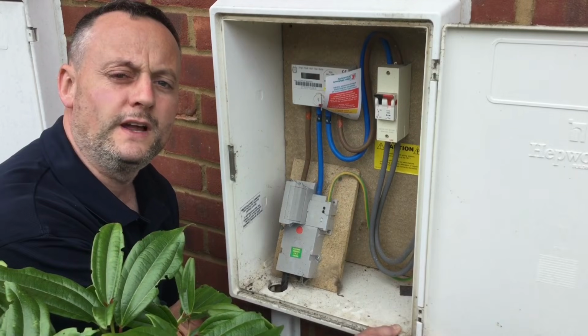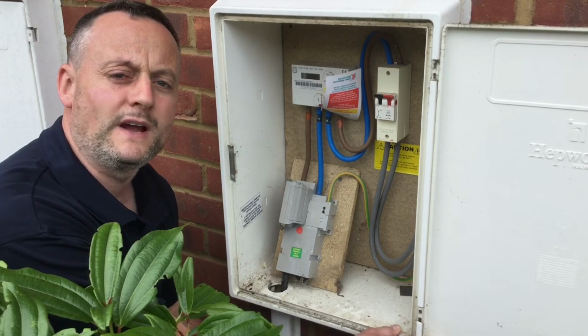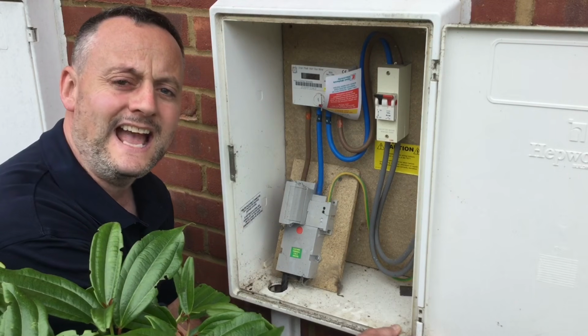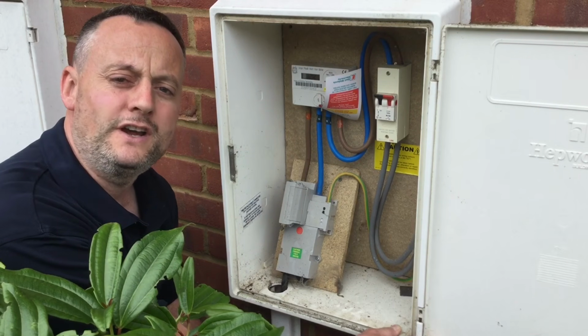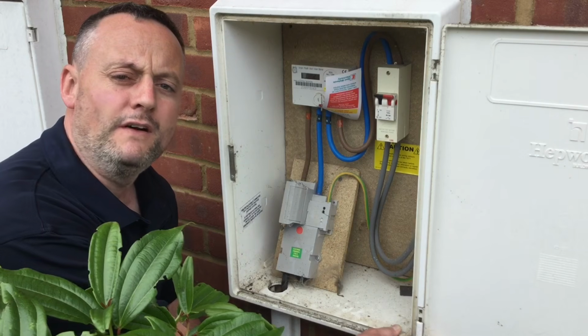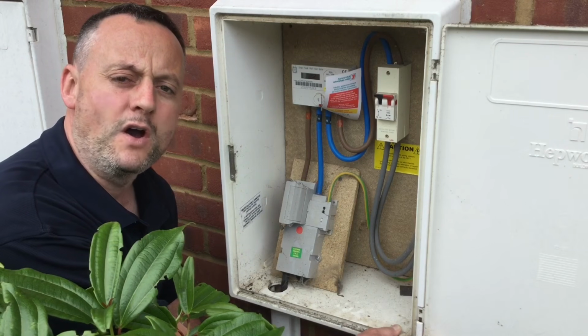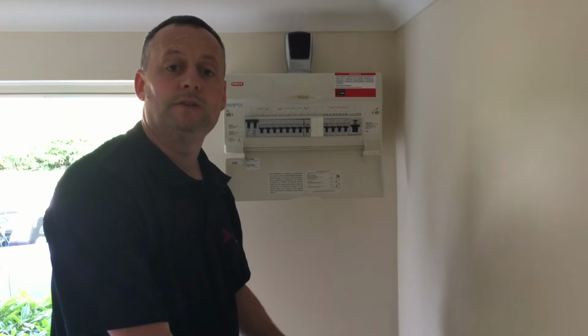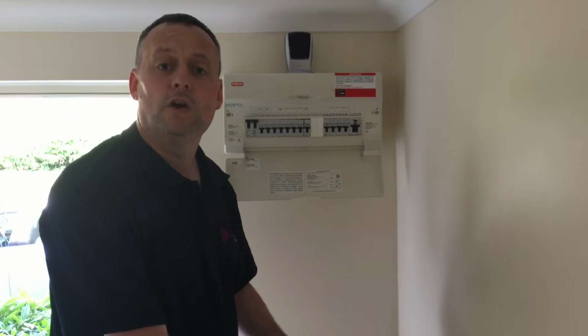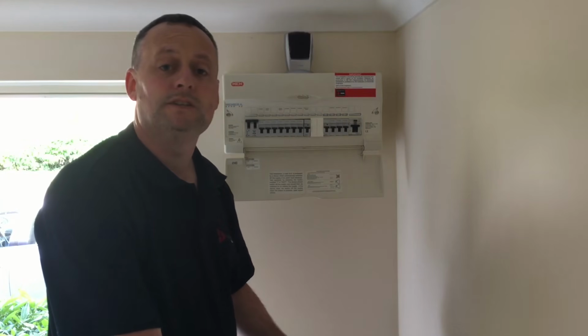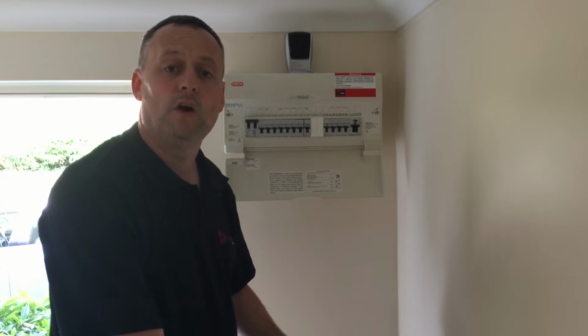Also, as we move through the learning on our course, we'll also see how the earthing arrangement, in this case TNCS, has a maximum external earth fault loop impedance of 0.35 of an ohm. We've identified at the origin of the installation the earthing arrangement is TNCS. We're now going to carry out the external earth fault loop impedance test to confirm our external earth fault loop impedance is no greater than the maximum allowed for this installation, which is 0.35 of an ohm.